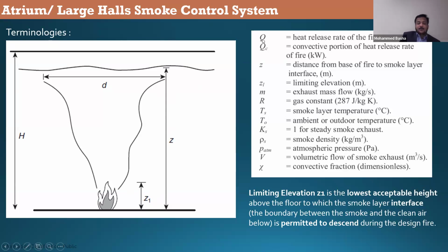In smoke management calculations, or in fire calculations, we use a letter called Q. Normally for HVAC engineers Q is GPM, or for plumbing engineers it's called flow rate. Here, Q means the heat release rate of the fire. Heat release rate, I will explain in the next slides, is the output of the fire, you can say. QC is called the convective heat release rate.